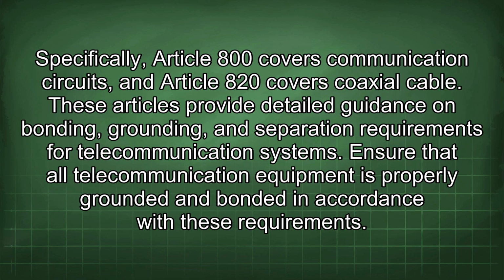Specifically, Article 800 covers communication circuits, and Article 820 covers coaxial cable. These articles provide detailed guidance on bonding, grounding, and separation requirements for telecommunication systems. Ensure that all telecommunication equipment is properly grounded and bonded in accordance with these requirements.